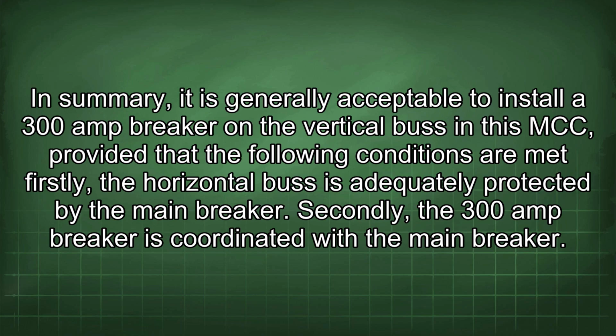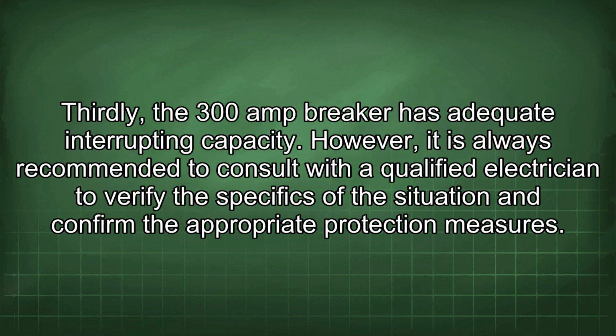In summary, it is generally acceptable to install a 300 amp breaker on the vertical bus in this MCC, provided that the following conditions are met. Firstly, the horizontal bus is adequately protected by the main breaker. Secondly, the 300 amp breaker is coordinated with the main breaker. Thirdly, the 300 amp breaker has adequate interrupting capacity.